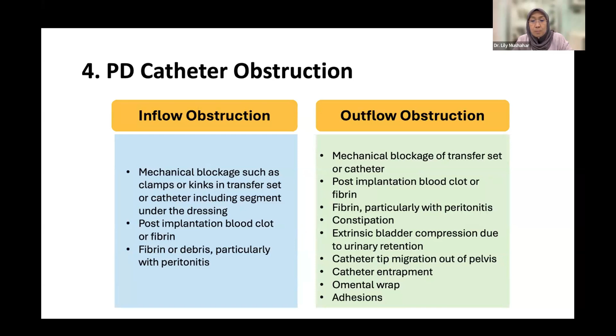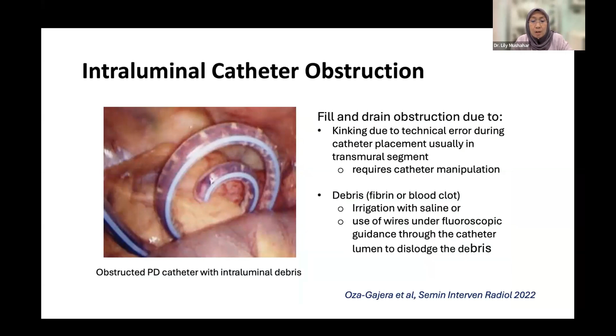This is a photo which shows intraluminal debris. It can be either fibrin or blood clots. For the fill and drain, you can flush the debris with irrigation and saline. Some operators use wires under fluoroscopic guidance, inserting the guide wire intraluminally to dislodge this debris. The other thing is how we should manage slow fill or slow drain, where there is no obstruction. You can still flush the PD catheter, but the drain is quite slow.